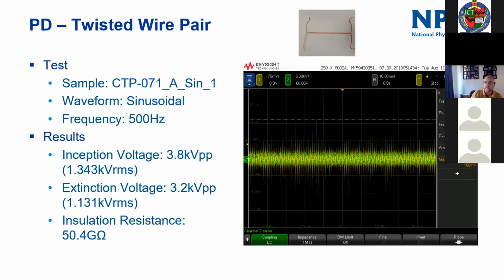So this shows PD within a simple twisted wire pair. This is a sinusoidal 500 hertz signal. That's the green signal. These graphs are not brilliant for display, but they're nice colors. But essentially, we're seeing an inception voltage there. The PD is the yellow signal in the background, and you can see these spikes occurring pretty much twice every cycle, as you go up through the sine wave and then back down through the sine wave. They occur somewhere around just under 4 kV peak to peak, which is about 1300 volt RMS with this particular sample. So it's above 1000 volts, but it is still below 1500 volts RMS, which is an interesting figure, which we'll talk about a little bit later.